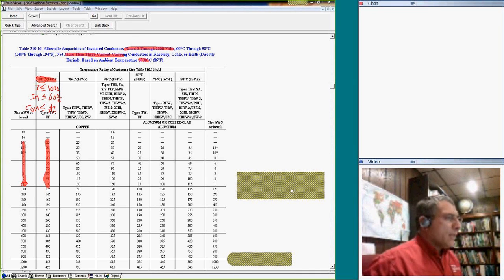Okay, let me go and write the other one, the 75-degree column. The 75-degree column, guys, is almost the same rule. I'm going to write them in a different color. I'm talking about the 75-degree column. Number one, let's look at the current. If your current is more than 100, then no problem. You're going to default to the 75-degree column.